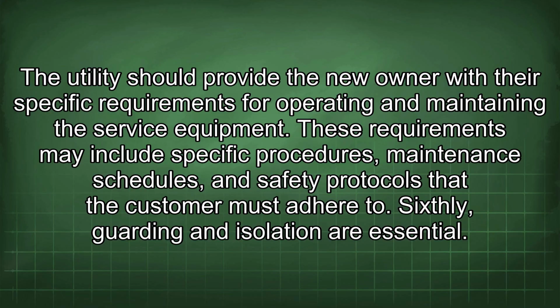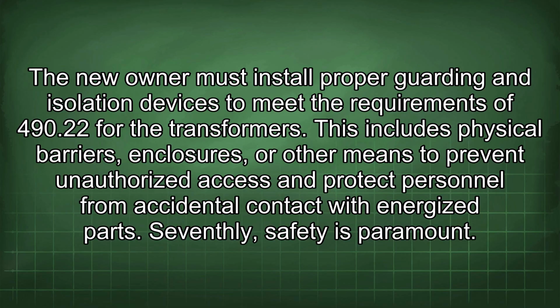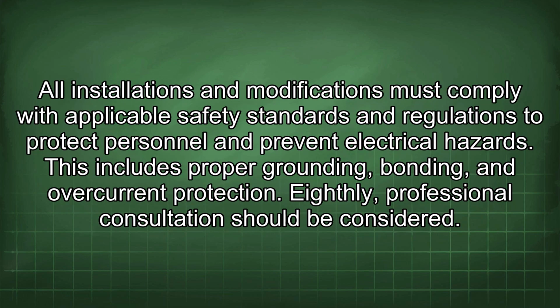Sixthly, guarding and isolation are essential. The new owner must install proper guarding and isolation devices to meet the requirements of 490.22 for the transformers. This includes physical barriers, enclosures, or other means to prevent unauthorized access and protect personnel from accidental contact with energized parts. Seventhly, safety is paramount. All installations and modifications must comply with applicable safety standards and regulations to protect personnel and prevent electrical hazards. This includes proper grounding, bonding, and overcurrent protection.